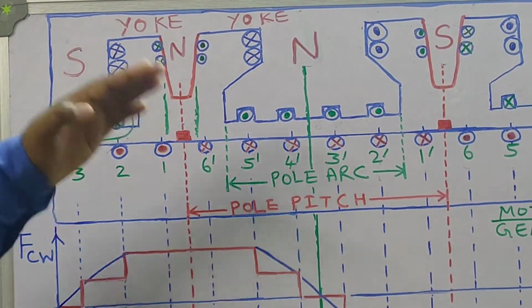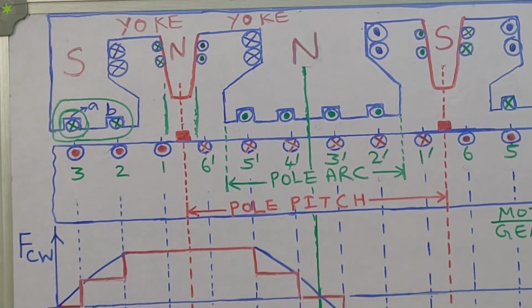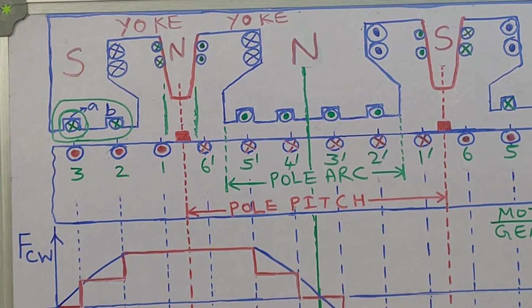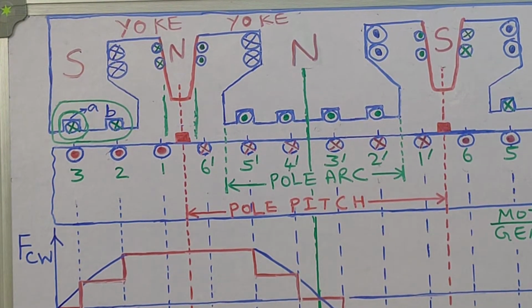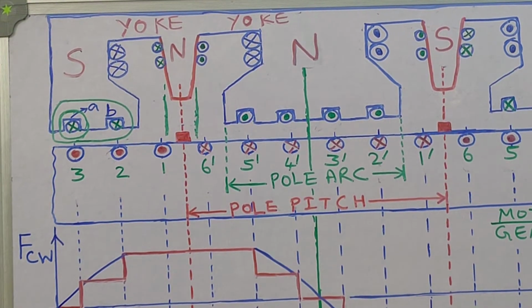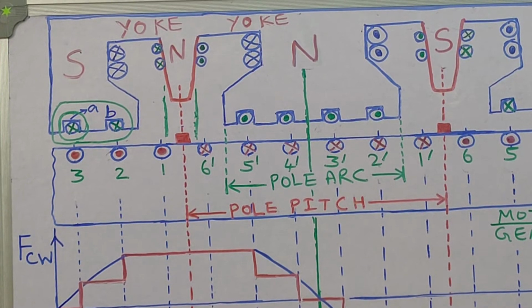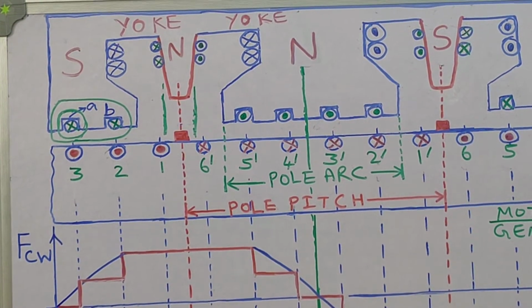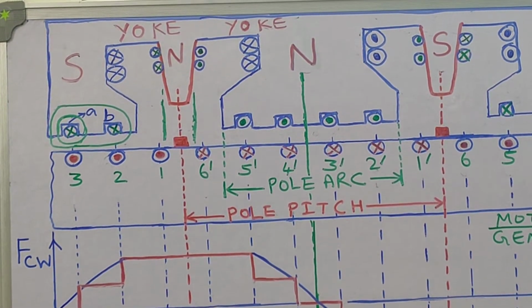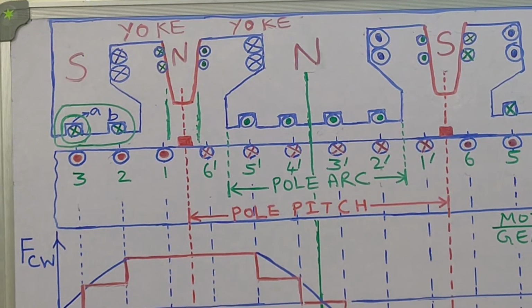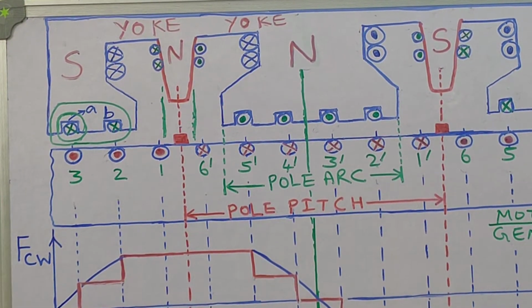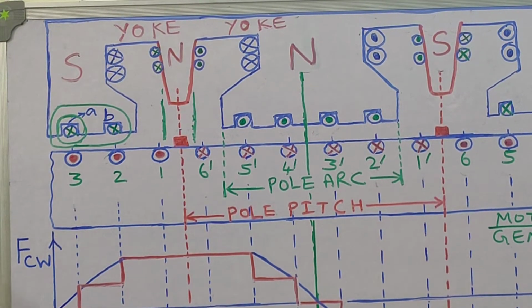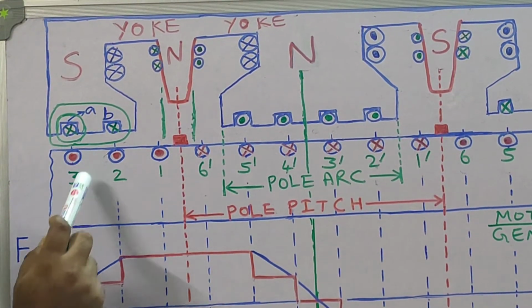So in order to make that happen, each and every time there is a change in load, there is a change in armature current. But in spite of that change in loading and armature current, the compensating winding conductors should be able to cancel the MMF due to the armature winding conductors. That is ensured by making sure that the compensating winding carries the same current which is being carried by the armature conductors. So what is done? They are connected in series.